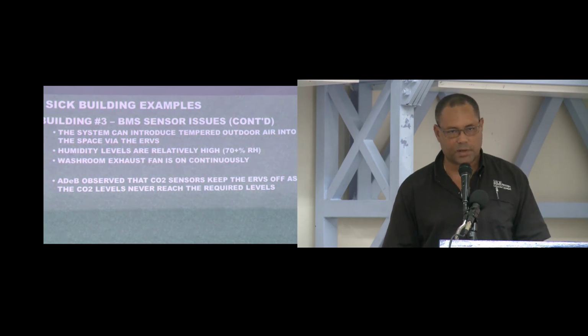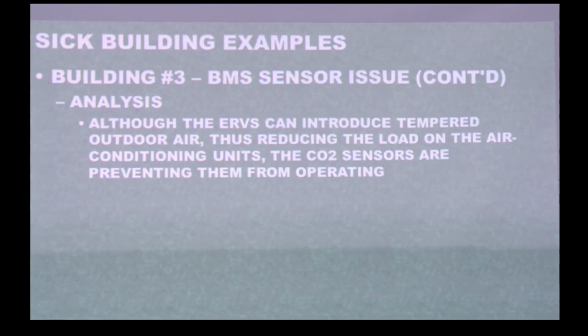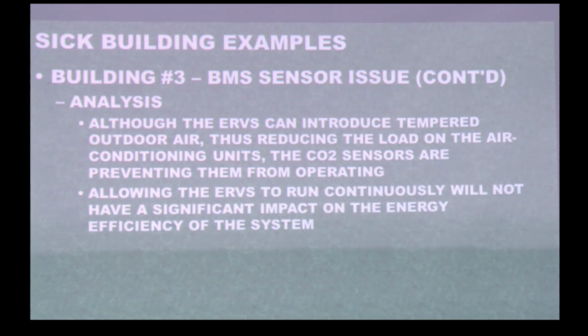You're getting air being brought in from outdoors, from the stairs below, through the actual ERVs that are off without actually tempering it. So you're penalizing your system by making it not be able to take advantage of the tempered air. So we're just sucking in air from anywhere that we can because we have to exhaust the washrooms. Nobody wants to smell the washroom coming back, right? That's what I was just talking about. The CO2 sensors are stopping the ERVs from operating.